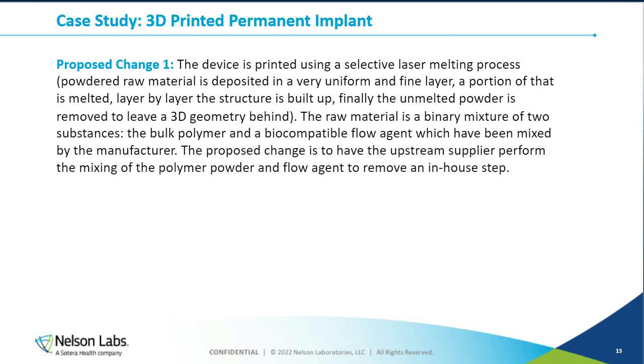So in this particular case, we have a permanent implant device that's selectively laser melted from a polymer powder. It's built up layer by layer. And then finally at the end, that powder is blown out and cleaned out, and this intricate 3D device remains. And in this particular case, the powder that was deposited is a mixture of the polymer and a small amount of flow agent, a well-known biocompatible flow agent, let's put it that way. And what was happening was that the manufacturer was buying the powder and also buying the flow agent, and they were mixing it themselves. And then that mix would be going into the printing process.